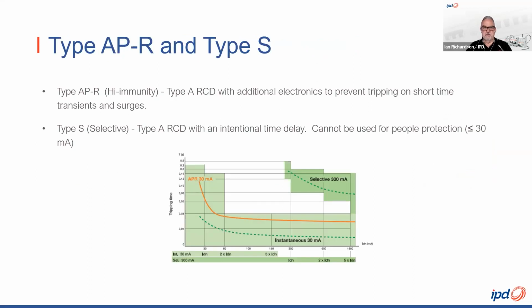We can look at some other styles of RCD as well. In the ABB range, we have high immunity models called an APR. These are actually a variation of a type A RCD with additional characteristics to prevent tripping on short-term transients and surges. In this graph, you can see the typical trip curve of an instantaneous RCD. It's that green dotted line towards the bottom there.